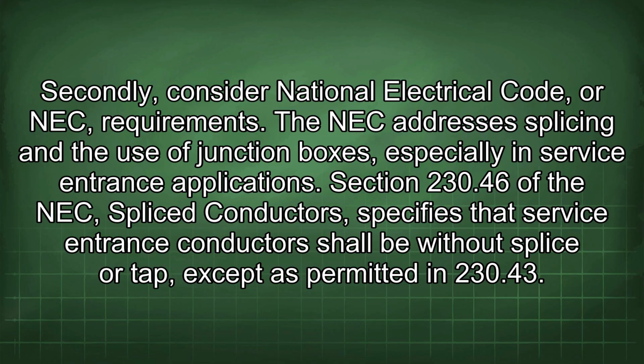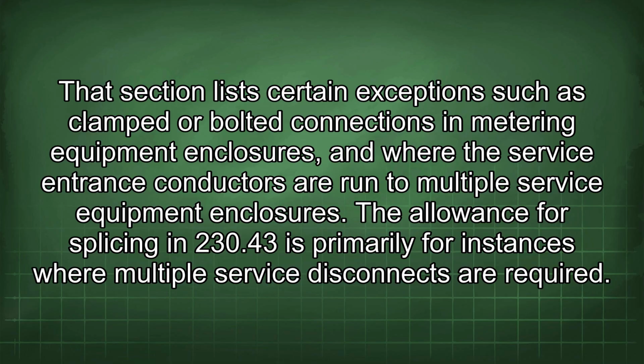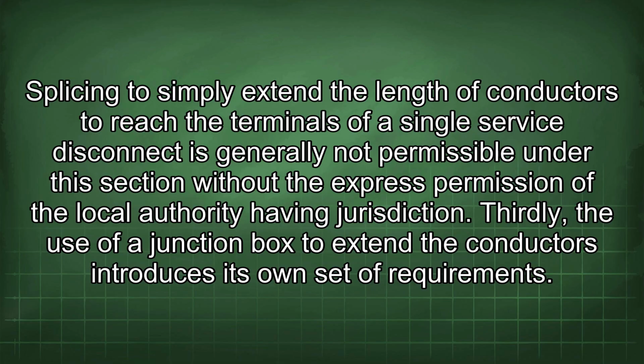Secondly, consider the National Electrical Code, or NEC, requirements. The NEC addresses splicing and the use of junction boxes, especially in service entrance applications. Section 230.46 of the NEC, Spliced Conductors, specifies that service entrance conductors shall be without splice or tap, except as permitted in 230.43. That section lists certain exceptions such as clamped or bolted connections in metering equipment enclosures, and where the service entrance conductors are run to multiple service equipment enclosures. The allowance for splicing in 230.43 is primarily for instances where multiple service disconnects are required. Splicing to simply extend the length of conductors to reach the terminals of a single service disconnect is generally not permissible under this section without the express permission of the local authority having jurisdiction.